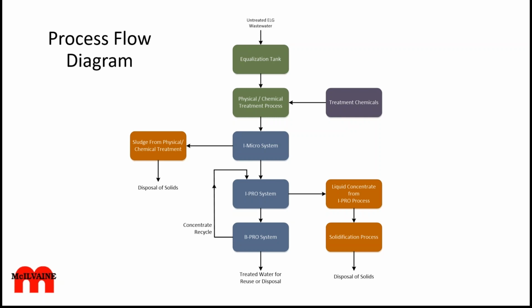Our systems are fully remote monitoring, custom design systems, so we typically monitor the influent pressures, conductivities, TDS set points, as well as the effluent. And you see a nice graph that shows the whole batch continuous graph and can tell everything going on with the system and the chemical feed rates, ensuring the system can be run with minimal operational labor. It's important to minimize chemical consumption while avoiding buildup and having to shut down your membrane system.